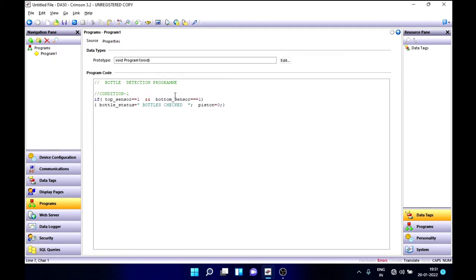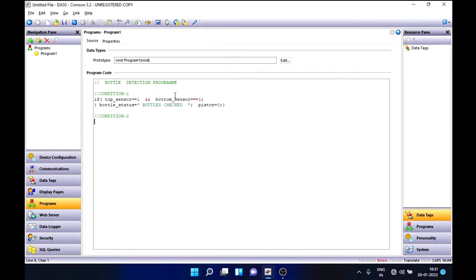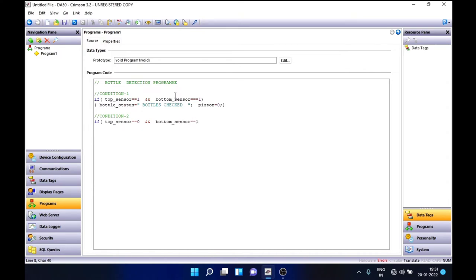Now let's come to the second condition. This is the condition where the bottle is fallen. The top sensor won't be sensing, so we get a value of zero from the top sensor, and only the bottom sensor will be sensing. This means the bottle has fallen due to vibration or something like that. In this condition, the bottom sensor will be one.